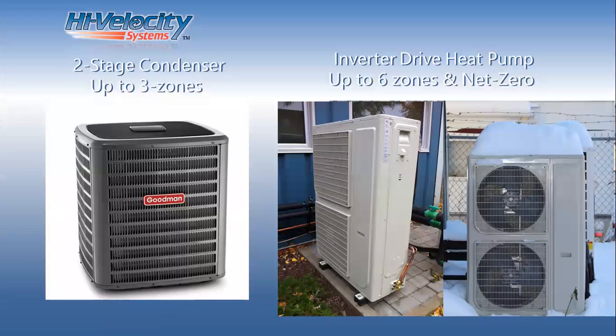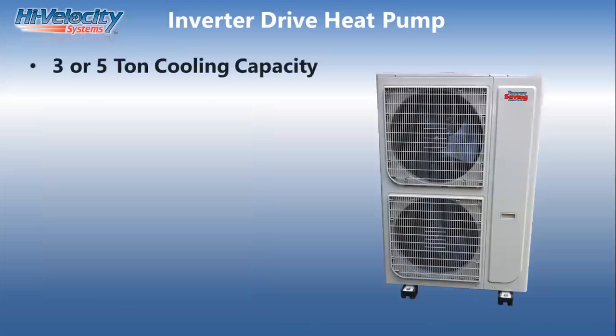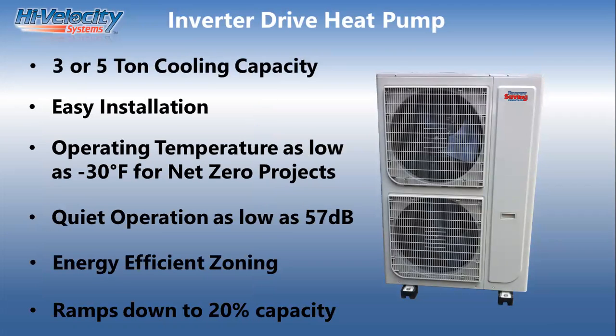When it comes to zoning air handlers, we strongly recommend more efficient, better technology than the traditional low SEER fixed speed. So we suggest 2-stage condensers on up to 3 zones. And if you're going past 3 zones on a single air handler, we look at chilled water or something like our manufactured inverter drive heat pump. We have our own inverter drive heat pump in the marketplace. It says here 3-ton and 5-ton cooling capacity. We now have a 2-ton product available. It's rated down to -30 Fahrenheit for heating operation, which allows us to present this as a net zero option in the markets that are doing net zero styles of installations.